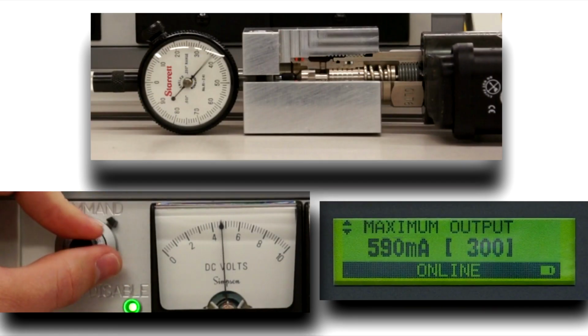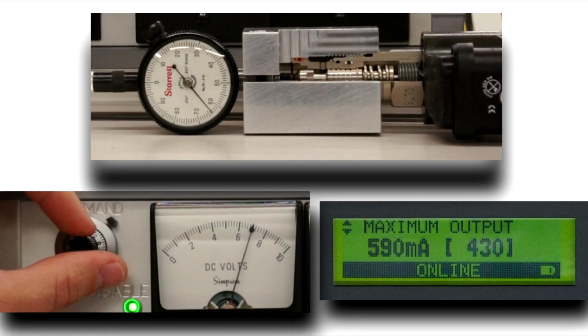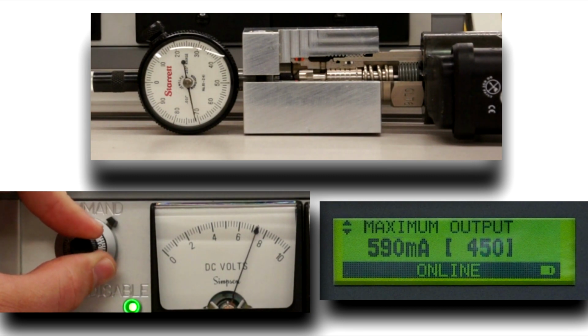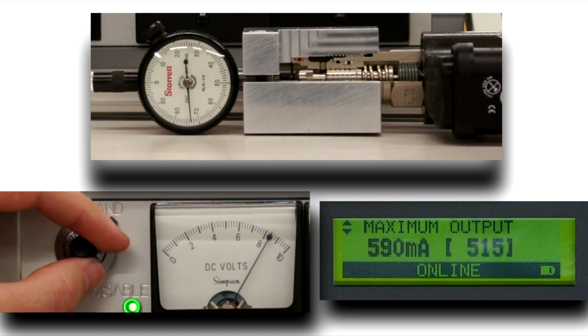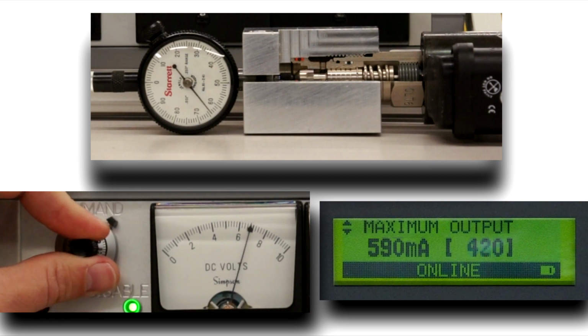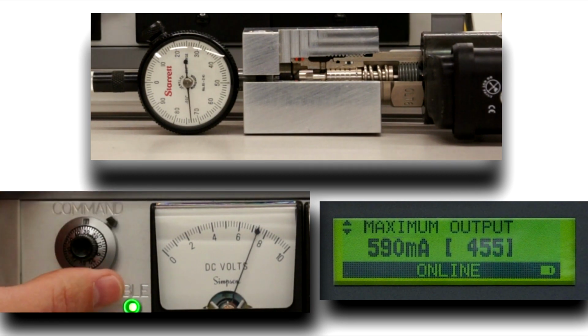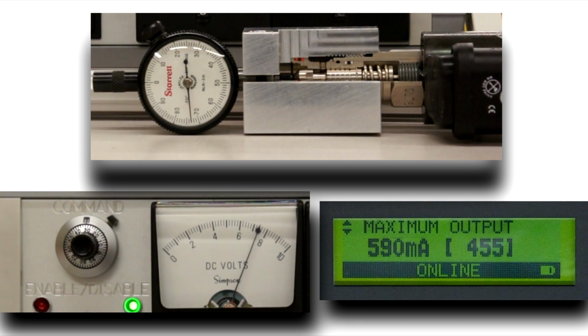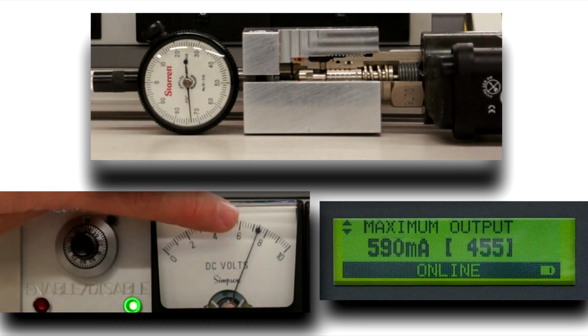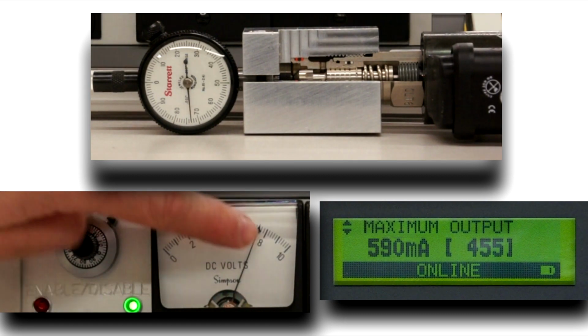The deadband can also be tuned out on the high side of the input. What you can do then is scroll down to the maximum output parameter. You'll notice as we ramp up the input, we'll get to a point where some amount of current will fully stroke the valve. In this case, you'll see that it only took about 455 milliamps to fully stroke the valve open. The remaining output current from 455 to 590 milliamps is wasted.